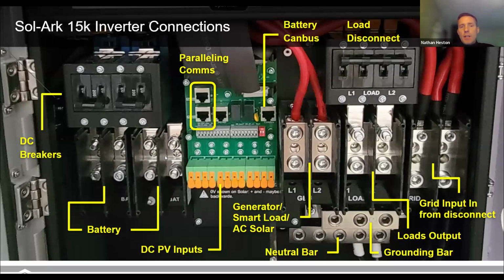Then your negative battery connections are here. In the center is a comms board, but on that comms board is also the input for the DC solar. So this is independent MPPTs. 4 of these lever cam lock inputs go to each MPPT. So positive, negative, positive, negative. And so these are your solar inputs. The MPPTs, sorry, positive, positive, negative, negative.